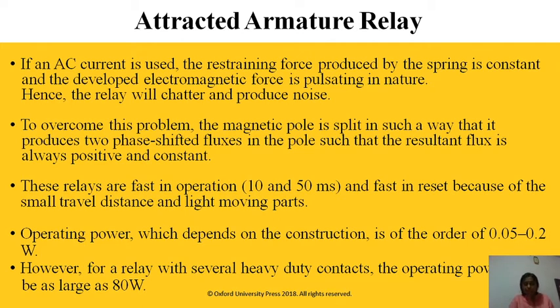Because of this problem, the relay will chatter and produce noise. As we have a frequency of 50 hertz, which means in 1 second we have 50 cycles, 50 times it will be on and 50 times it will be off. This on and off goes on continuously, so it will produce noise and finally it will not operate. So we need some improvement in that electromagnet, which I will tell.